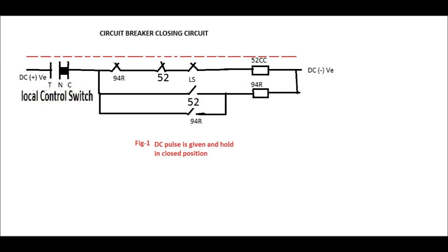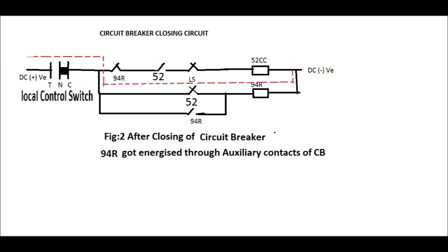When a DC pulse is given from the control switch and we hold the control switch in the close position — that is, a continuous DC pulse is given from the TNC switch — the closing coil 52CC will energize through the NC contact of 94R, the NC contact of 52, and the limit switch contact. Whenever it energizes, it will operate the circuit breaker to make it ON. When the circuit breaker is in the ON condition, the auxiliary contacts of the breaker change their positions, and the DC pulse will bypass through the NC contact of the breaker, which was previously in the NO position, thereby energizing the 94R relay.